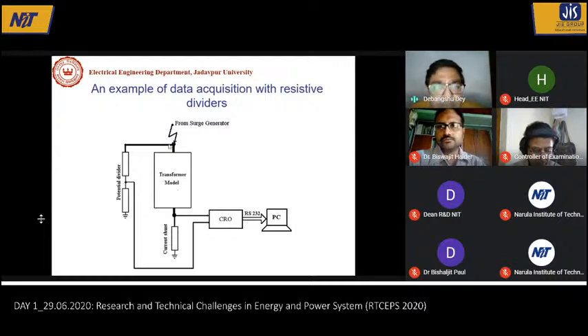The surge or impulse is applied across the transformer winding, and we have to check whether that voltage waveform is as per standard or not. We can measure that voltage using a potential divider, because the impulse voltage is of very high magnitude and cannot be directly recorded using a CRO. So we use a potential divider, as well as a current shunt or current acquiring device, to record the winding current.